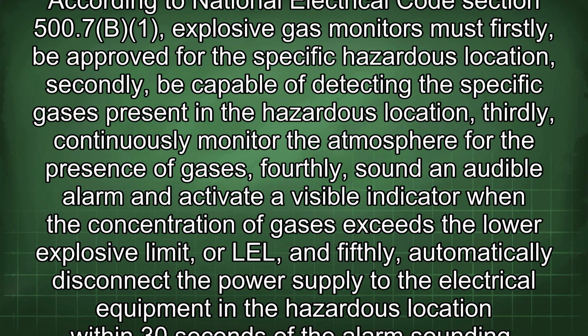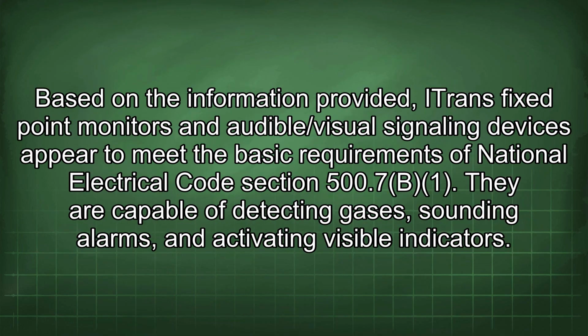for the presence of gases, fourthly, sound an audible alarm and activate a visible indicator when the concentration of gases exceeds the lower explosive limit, or LEL, and fifthly, automatically disconnect the power supply to the electrical equipment in the hazardous location within 30 seconds of the alarm sounding. Based on the information provided, ITrans fixed-point monitors and audible/visual signaling devices appear to meet the basic requirements of National Electrical Code Section 500.7(B)(1).